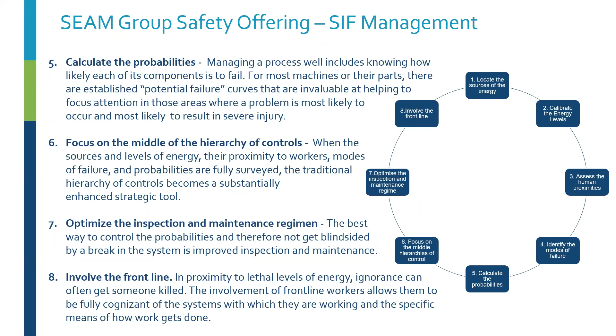But we can get upstream of that. We now have a technology in arc flash relays that allows us to massively mitigate, reduce the amount of energy dispersed in the event of an arc flash. Ultimately, a good systemic approach to that particular risk is about redesigning equipment to largely eliminate the possibility of an arc flash causing permanent disability or death. That technology is available to us, and again, it's getting way upstream and getting much higher in the hierarchy of control.